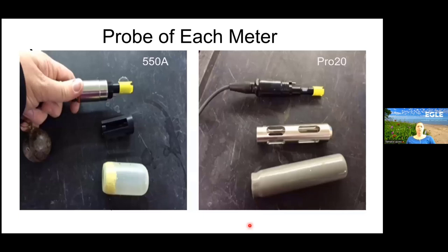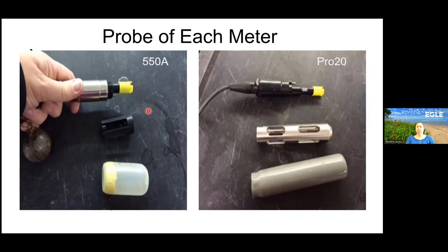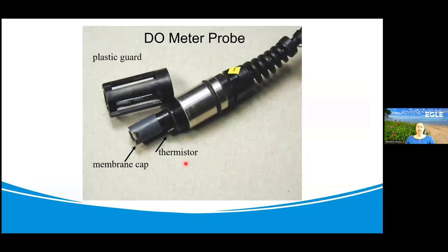Here is what the probe looks like when we take the cover off — there's a cage that protects the membrane, and the membrane itself goes over the oxygen probe in the middle. We don't want you to touch the yellow portion that encloses the membrane because it can be damaged very easily — it's very fragile. The little silver part visible on the probe is the thermistor, which measures the temperature.